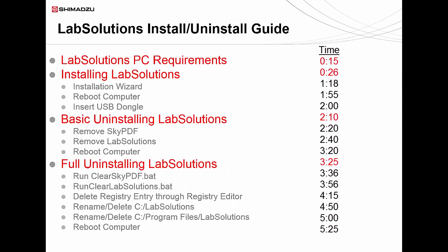This is a video guide on both how to install LabSolutions WorkStation software as well as how to perform a basic or full uninstall of LabSolutions software. The PC requirements to run LabSolutions are shown here. Although LabSolutions can be installed in a 32-bit operating system architecture, we recommend a 64-bit architecture.